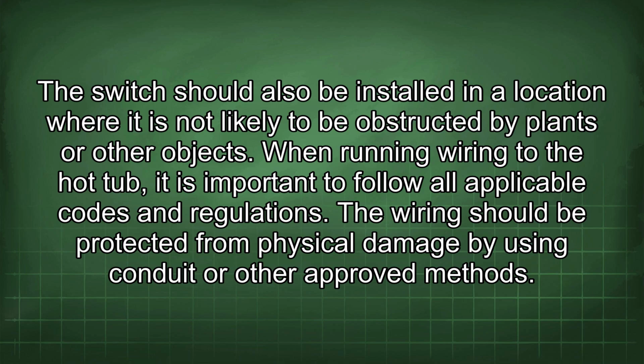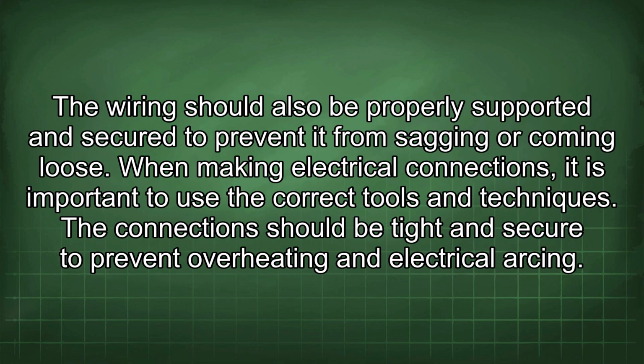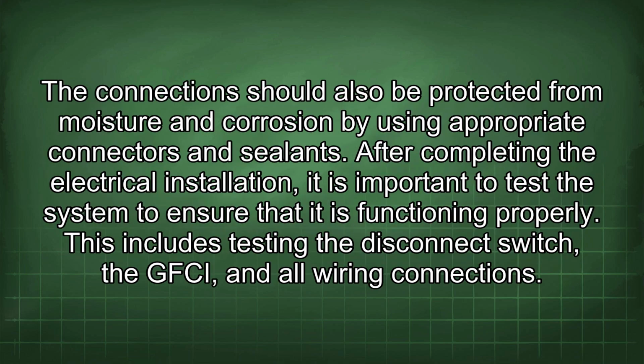The wiring should be protected from physical damage by using conduit or other approved methods. The wiring should also be properly supported and secured to prevent it from sagging or coming loose. When making electrical connections, it is important to use the correct tools and techniques. The connections should be tight and secure to prevent overheating and electrical arcing. The connection should also be protected from moisture and corrosion by using appropriate connectors and sealants.